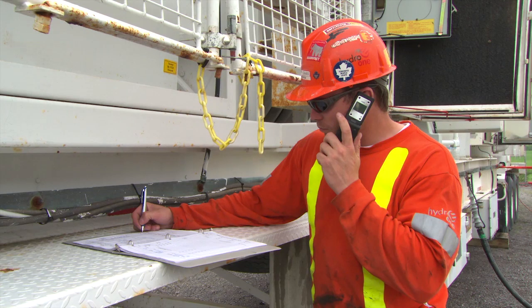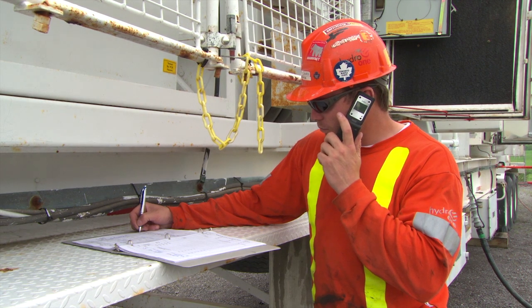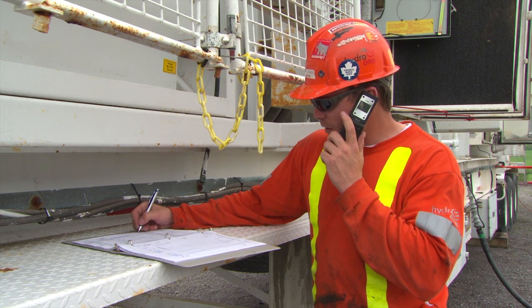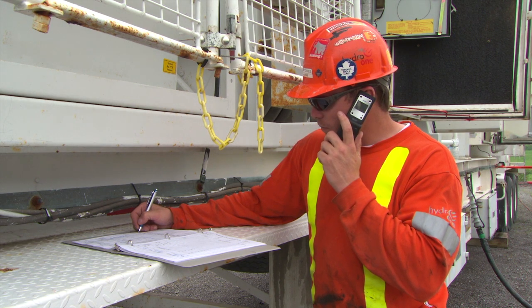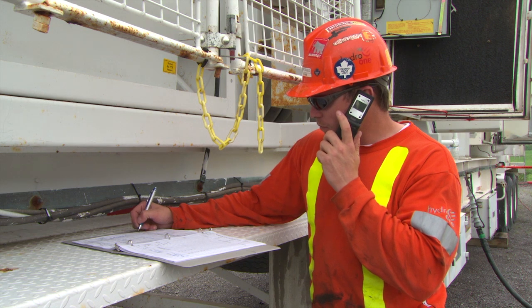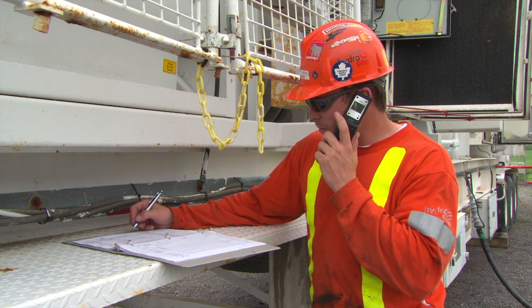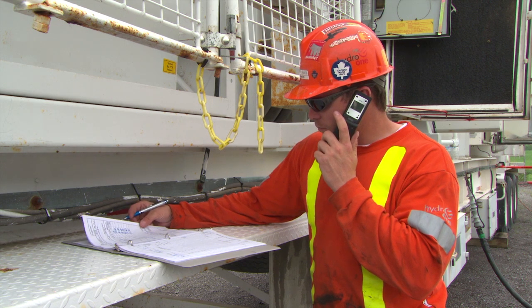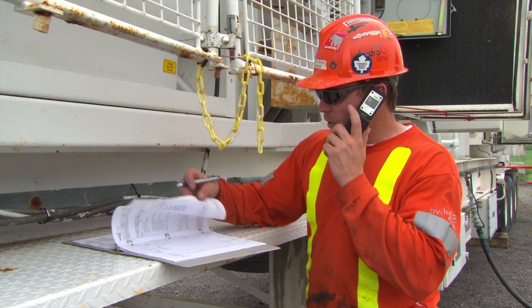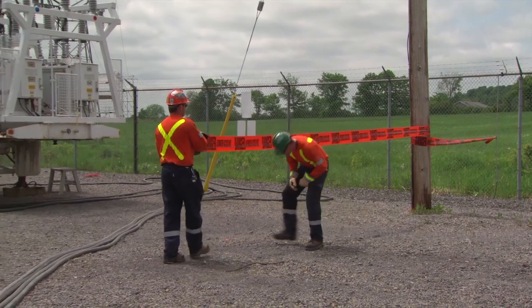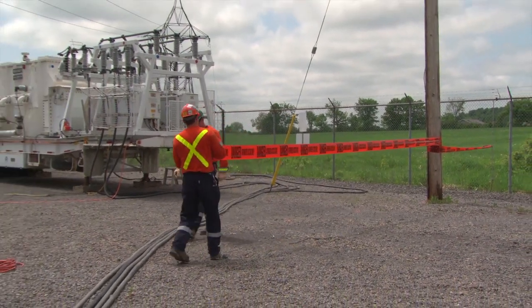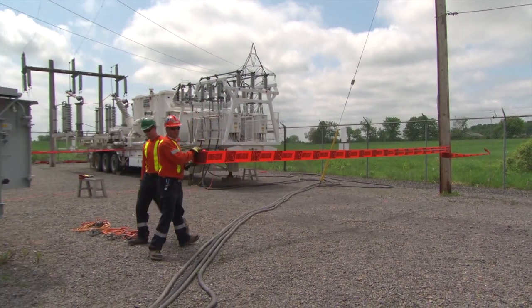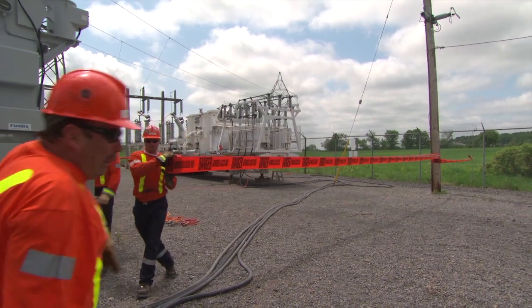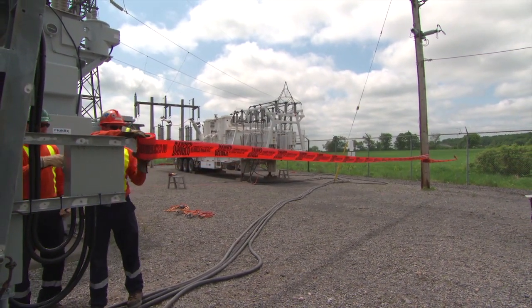Surrender the hold-off on the high-voltage 115 kV circuit. Contact the controlling authority to inform them of the DS and MUS status. If the controlling authority is Provincial Lines, the DOMC must also be informed. Establish a self-administered work permit on the DS equipment if required. Install additional barriers to prevent vehicle or pedestrian traffic from approaching the MUS installation or crossing the low-voltage cables on the ground.